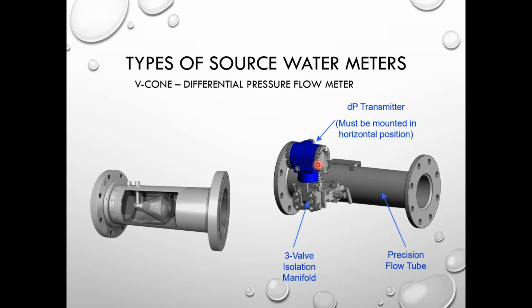And the DPI indicators that are out on the market are Foxboro, E&H, and Rosemount make a DPI, and it's able to read very accurately the pressure that's built up from going around the cone segment. So we have a high pressure port here and a low pressure. The low pressure port is reading the pressure after the cone. The high pressure is reading before it.